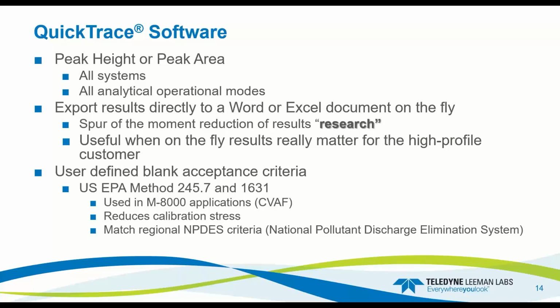So we have applications where we run it at, say, 1.5 minutes per sample, maybe under peak height or peak area with a little higher gas flow and a higher pump rate. You can run it in as little as 45 seconds per sample. We can also export or copy the results, export them right into a Word or Excel document while it's running. That's useful if somebody wants a number right now, a high priority or a stat sample. You can pop it in the system, get the results, do the math on it and get the customer's report. We also have user-defined blank acceptance criteria, which is mainly for US EPA 245.7 and 1631.